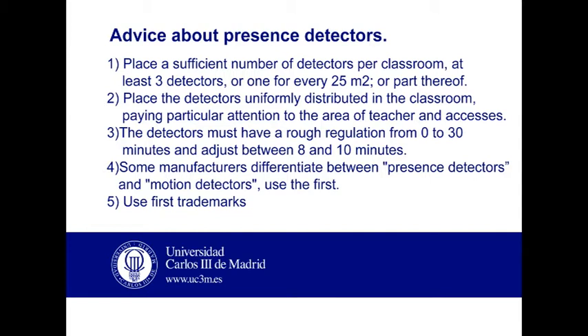2. Place the detectors uniformly distributed in the classroom, paying particular attention to the area of teacher and accesses. 3. The detectors must have rough regulation from 0 to 30 minutes and adjust between 8 and 10 minutes.